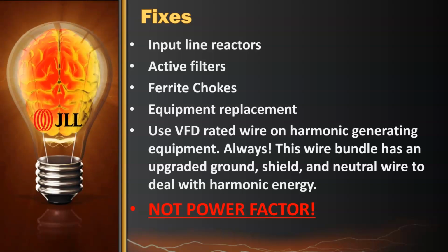These days, to get that granularity so that the meter can operate the same way the old mechanical one did, because what they used to do was test the old mechanical meter against the new electronic one, and the old mechanical meter was always more accurate. And so the meter manufacturers got more and more intense about measuring a smaller and smaller time slice. Now it takes the 60 hertz waveform and chops it up into 100,000 pieces, very, very small. Well, great. It does a good job competing against the mechanical meter, but it goes for the head fake of a transient or harmonic voltage, and it reads all of that stuff every single time.